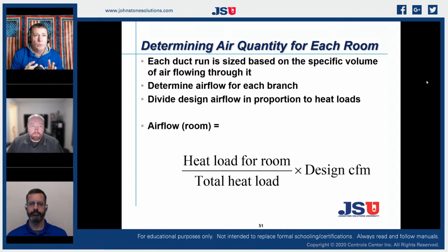So when we are looking at ductwork, we're going to decide what static pressure we need to use to calculate our size of ductwork. In this particular example, we're just going to stick to 0.1, just so we can get the understanding and see it easily on our duct calculator. So if anyone has a duct calculator with them, this would be a very good time today to look at what we're talking about on a duct calculator.